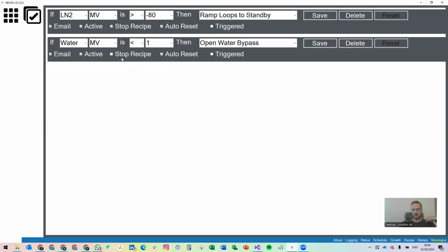So this is how you build up rules. The idea of the Watchdog is you use it mostly to monitor the services on the system, but you can use it to catch things like when the thermocouples break on the system, because there's a step change in the temperature that the PID controller will see. You can build up rules for anything in the system to protect the system. And this is so critical to MBE, where you can suffer a lot of downtime and a lot of damages.